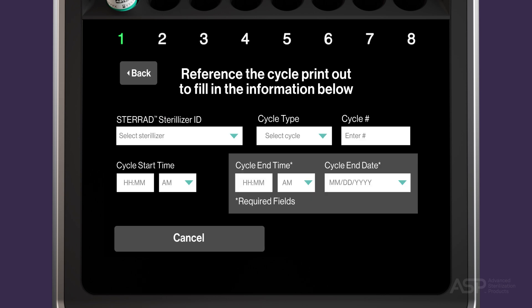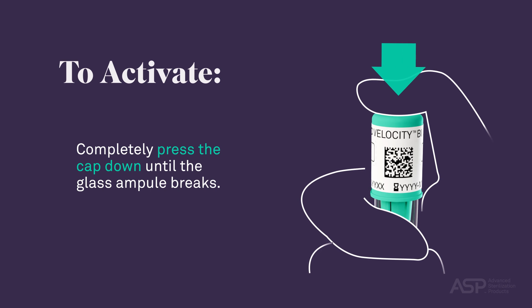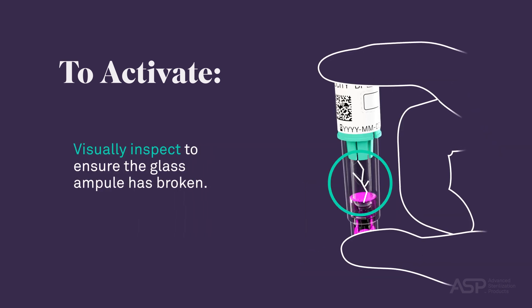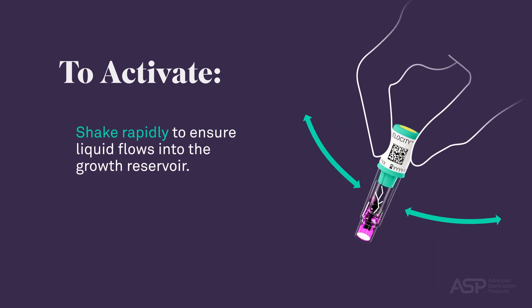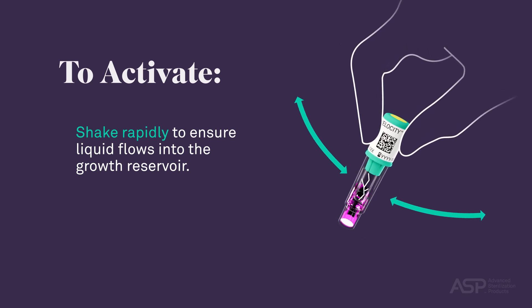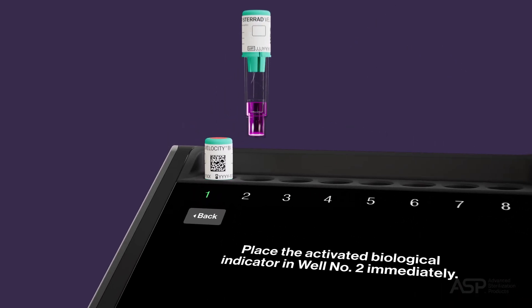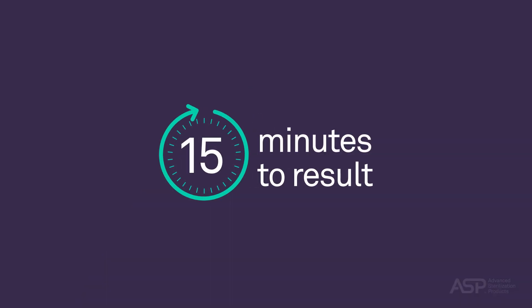Complete the required information fields before touching Next. This information can be found on the cycle printout from the corresponding STERRAD sterilizer. To activate the BI PCD before placing it in the reader, completely press the cap down until the glass ampule breaks, then visually inspect to ensure the glass ampule has broken. Shake it rapidly to ensure liquid flows into the growth reservoir and fills it with no large bubbles present. Failure to do so may result in incorrect reading. Once complete, place the processed BI PCD in the selected reader well. Test results will be available in as fast as 15 minutes. Do not remove the BI PCD until incubation is complete, as doing so will void the BI PCD.